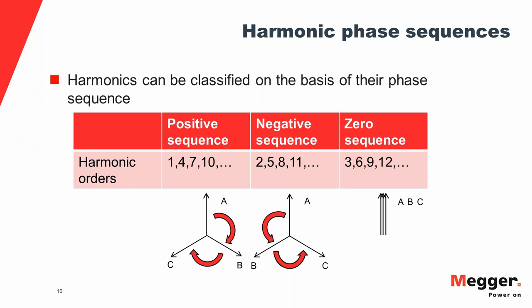Based on phase relationships, harmonics are classified into three categories: the fundamental, 4th, 7th, 10th, 13th — and so on — are positive sequence harmonics; the 2nd, 5th, 8th, 11th, 14th are negative sequence harmonics; and multiples of the third harmonic — the 3rd, 6th, 9th, 12th — are zero sequence harmonics.